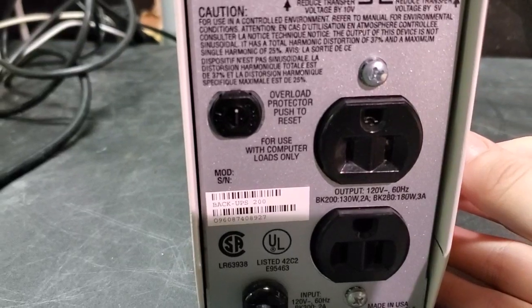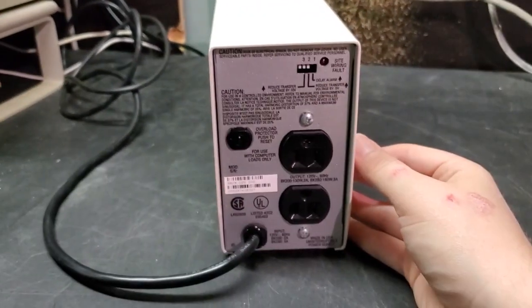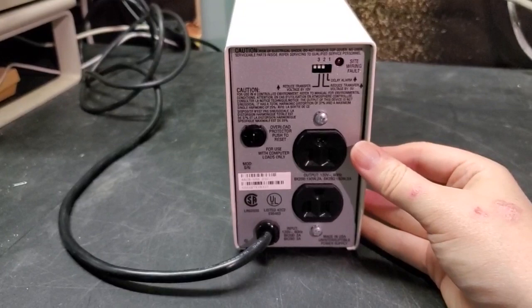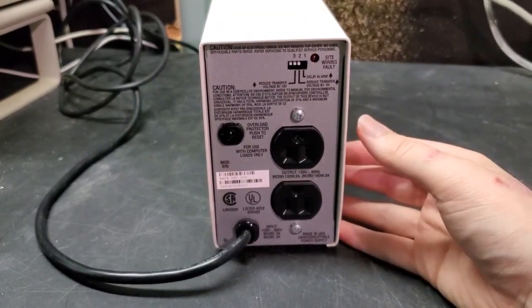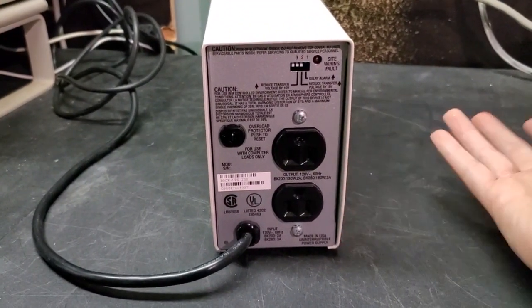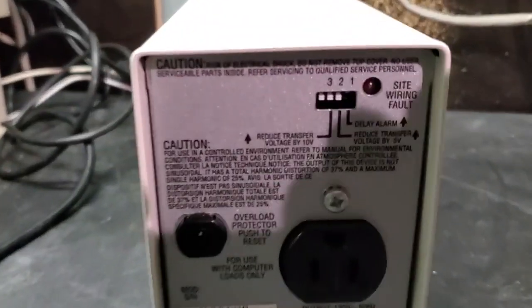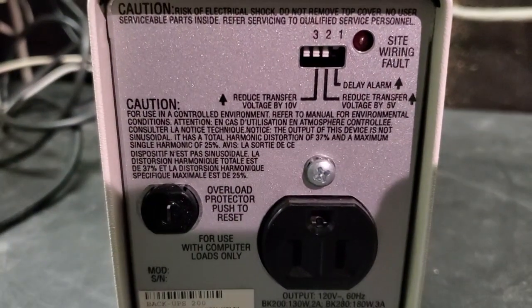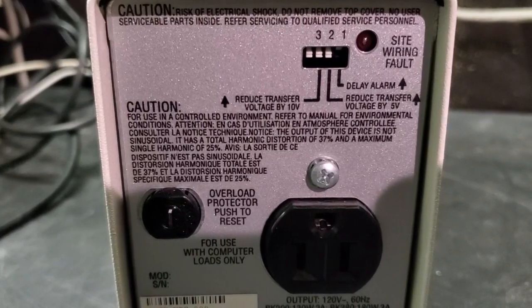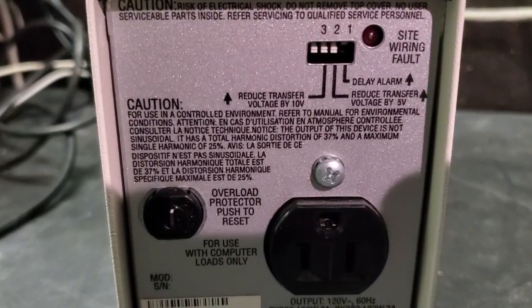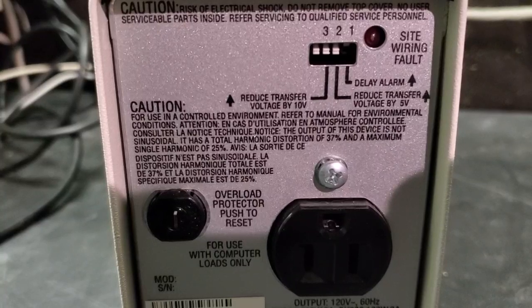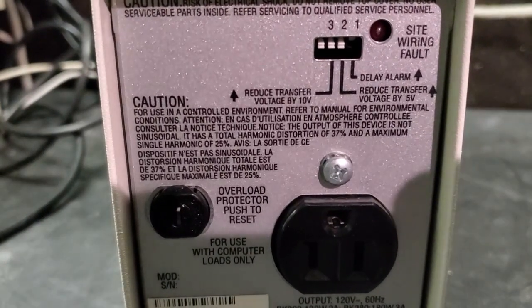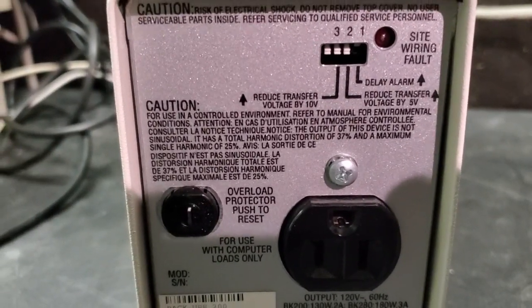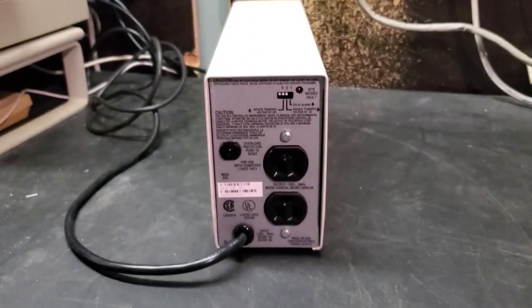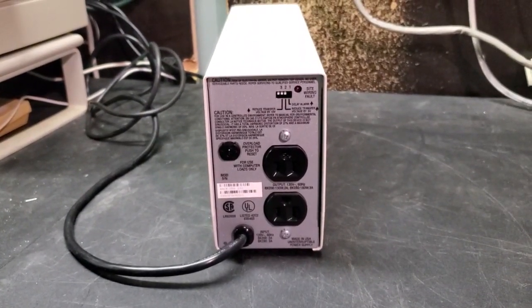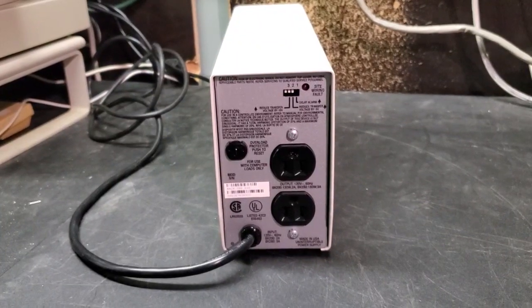Funny here, it says for use with computer loads only. So they don't want you to do something like plug an incandescent lamp into this thing, but I will do that as one of the tests. For use in a controlled environment, refer to manual, and so on. The output of this device is not sinusoidal. It has a total harmonic distortion of 37% and a maximum single harmonic of 25%. And that's all on account of it being a modified sine wave. It's basically saying the waveform output of this thing is very, very dirty.